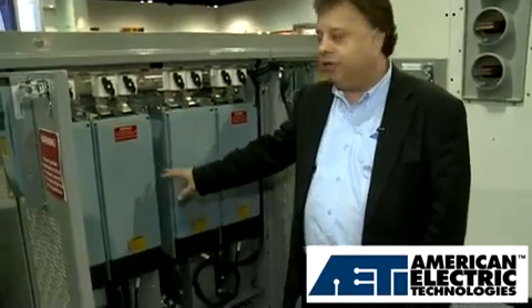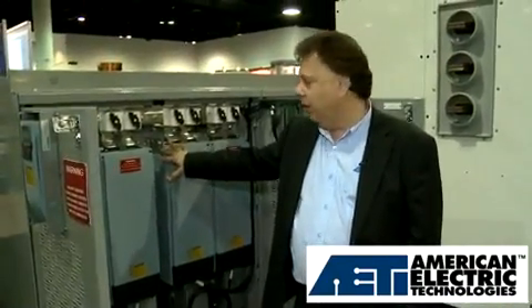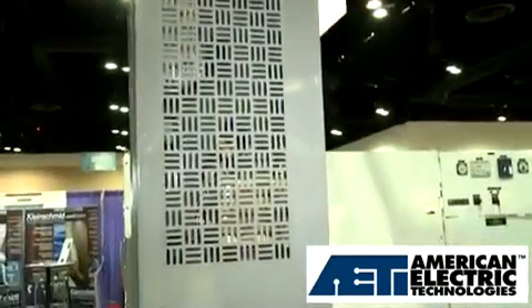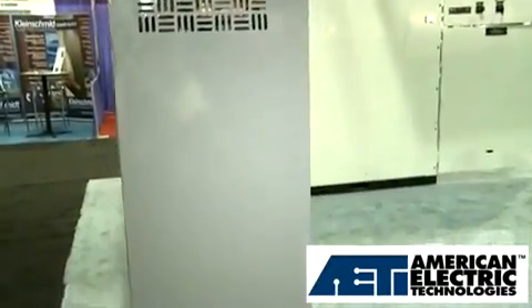And what we have here is 2 megawatts worth of fields that come out of that generator and come into this system. These are two air-cooled units that we have inside the base of the turbine, and you can notice that it's a very compact turbine. It's very narrow. It goes through the door. It's one of the features of our converter that other people don't have.